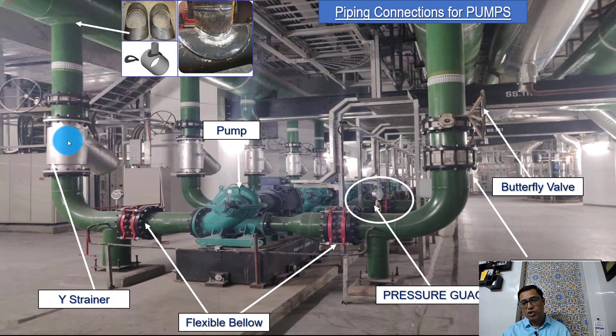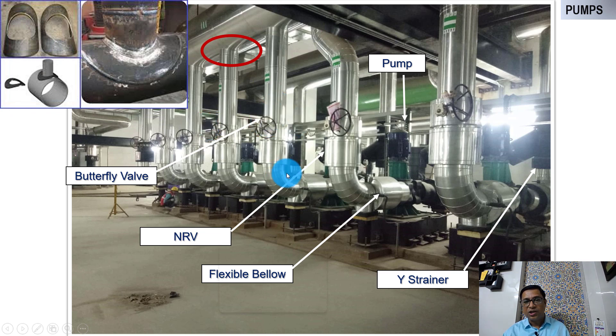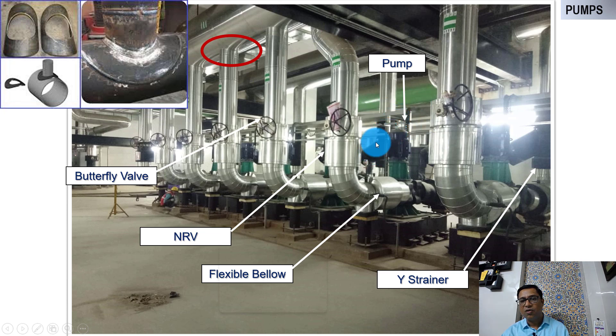The one I showed you earlier is for the condenser water system — you can see the pipes are bare. Now the one I am going to show you is the chilled water system, and that is why the pipes are insulated with cladding. We can see here the isolation valve — butterfly valve. This is a discharge line, so we have an NRV over here. These are the flexible bellows — gone inside the cladding. We have a strainer over here on the suction side. You can see a butterfly valve and then a strainer, and this is the pump. This is how the pump piping connections are done.